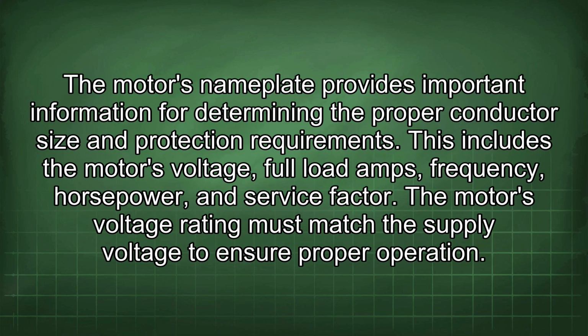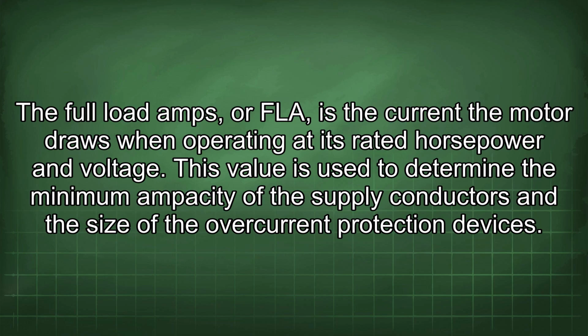The motor's nameplate provides important information for determining the proper conductor size and protection requirements. This includes the motor's voltage, full load amps, frequency, horsepower, and service factor. The motor's voltage rating must match the supply voltage to ensure proper operation. Full load amps, or FLA, is the current the motor draws when operating at its rated horsepower and voltage.